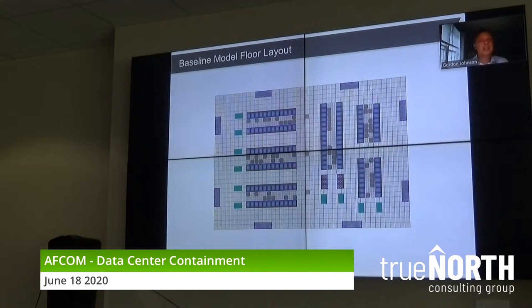Let's go to this data center that costs us about $840,000 a year to operate. Not too big, cold aisles, hot aisles. The blue you can see is the cold. The red on the racks is the hot. See the perf tiles down the aisles, standard flow. Then I've got some high flow, kind of the oval shape. They're in front of higher kW racks, you know, very common. You see the CRACs around the data center.